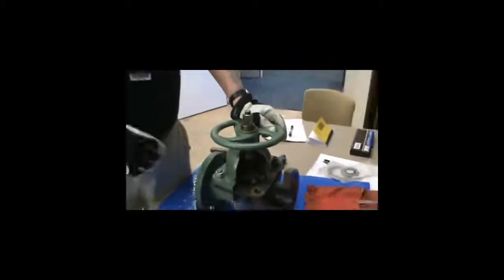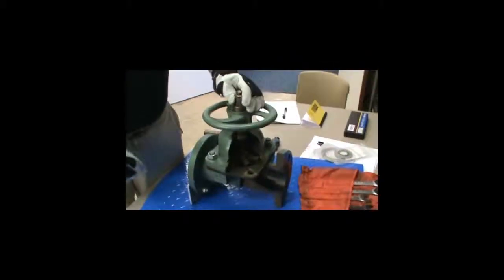Incorrect stroke, no matter how far you close it, the diaphragm is never getting to the weir, it will never seal, it will never pass leak rate tests.